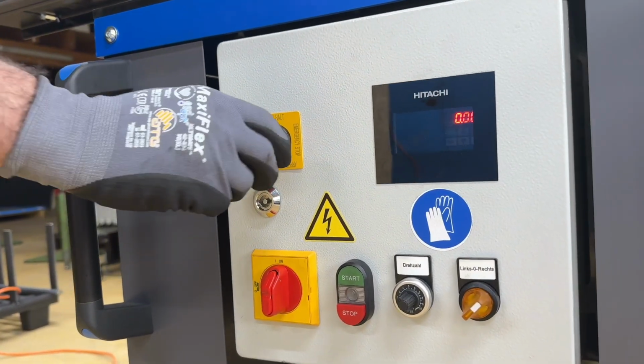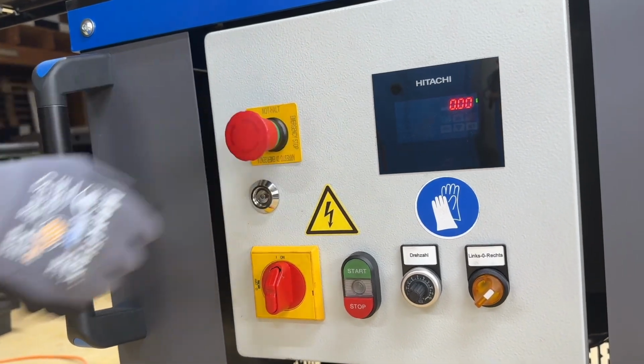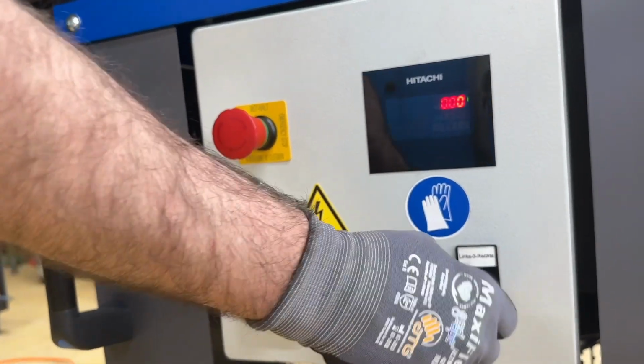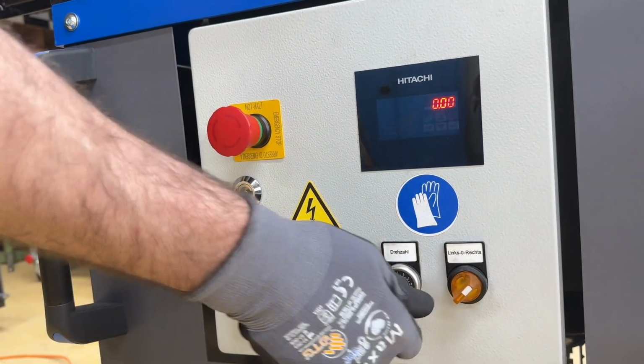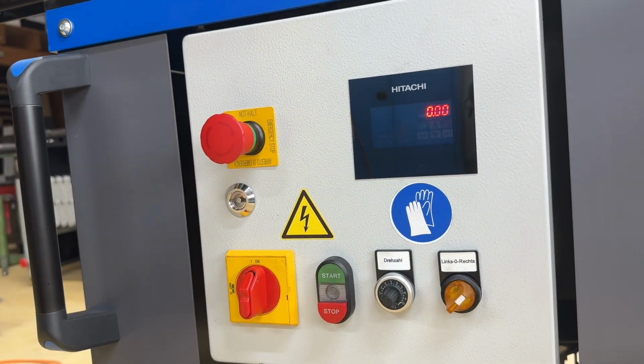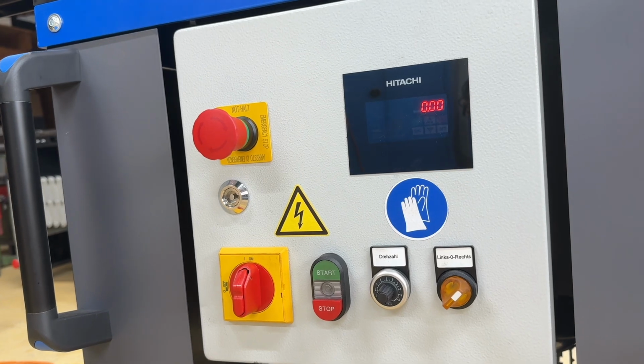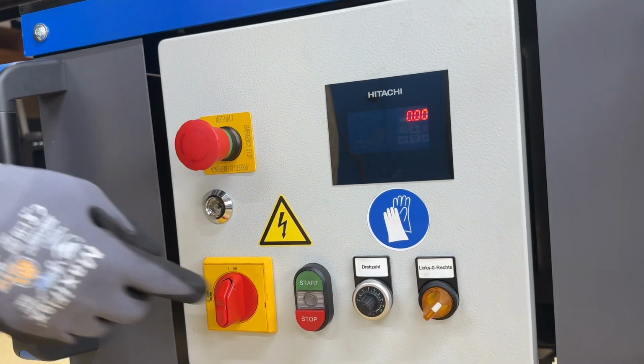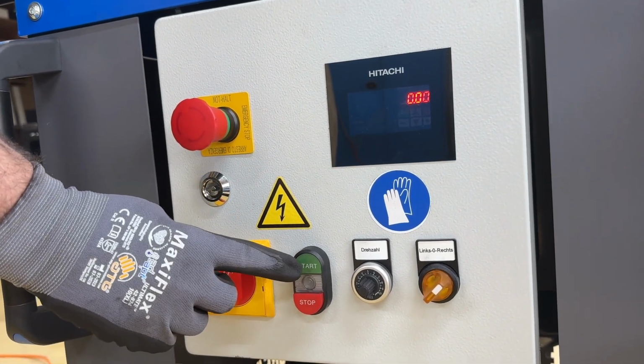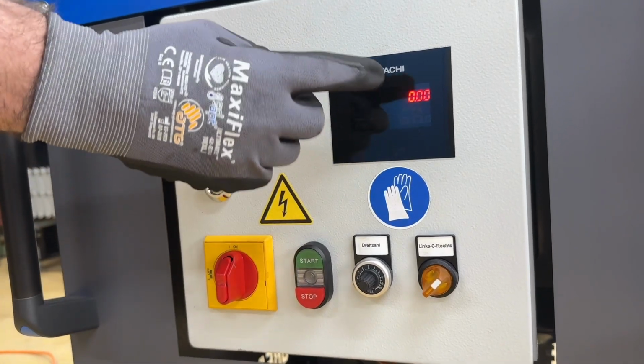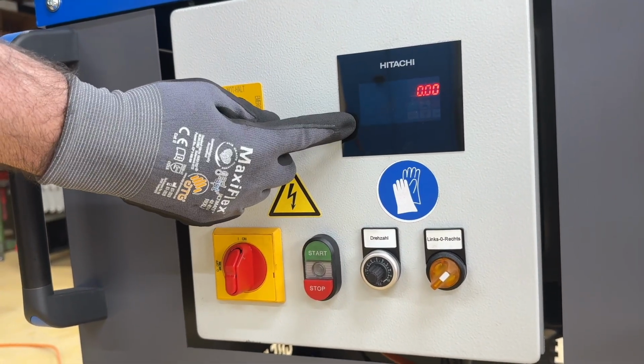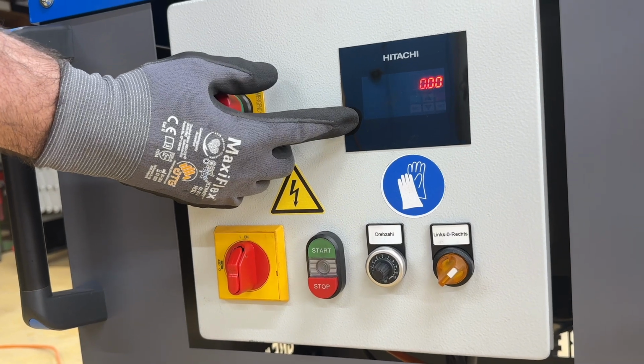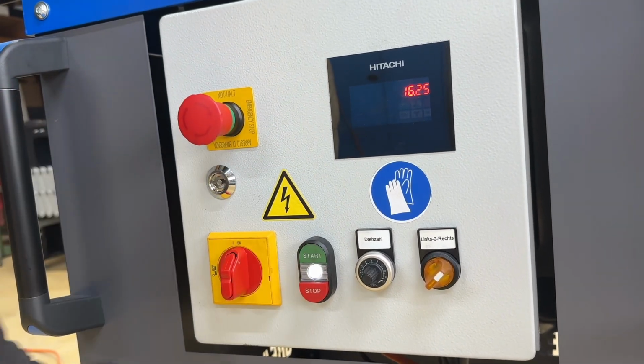Important. Check whether the main switch is switched on, the emergency stop is unlocked, the direction of rotation is correctly set to clockwise, and the speed is fully turned up. The inlet plate must also be inserted correctly. I should then be able to start the machine. I can see whether the machine is supplied with power by the frequency inverter, which displays a value of 00. Now I can start the machine.